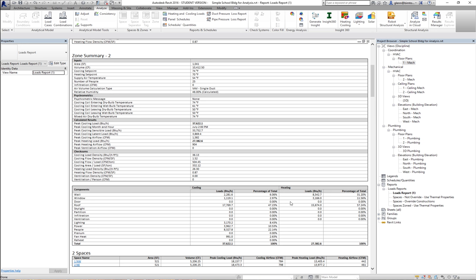The table shows what's contributing to the load. For the north zone with default assumptions, about 57% of heating and cooling is going through the roof surface — that's because we don't have a very good roof under these default assumptions. This gives you a sense of where to spend money if you're thinking about improving thermal properties: roof would make the biggest difference, then wall. Window isn't actually so bad, partially because we don't have that many windows on the north side.